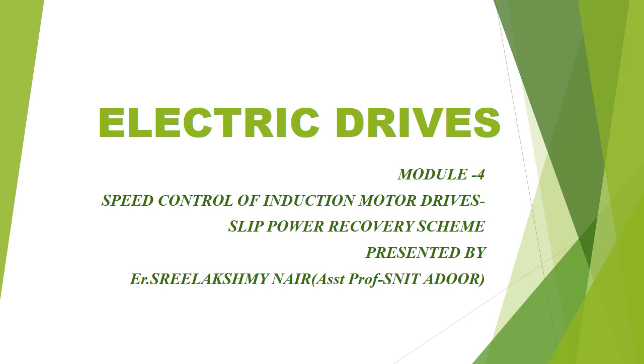Slip power recovery scheme is a method of speed control of a wound rotor induction motor — that is, a slip ring induction motor — in which some amount of rotor recovered power is fed back to the main supply instead of wasting it in the rotor resistance. In rotor resistance control, the slip power in the rotor circuit is wasted as I²R losses during low speed operation, reducing efficiency. Here, the slip power from the rotor circuit can be recovered and fed back to the AC source so as to utilize it outside the motor, thus increasing overall efficiency.